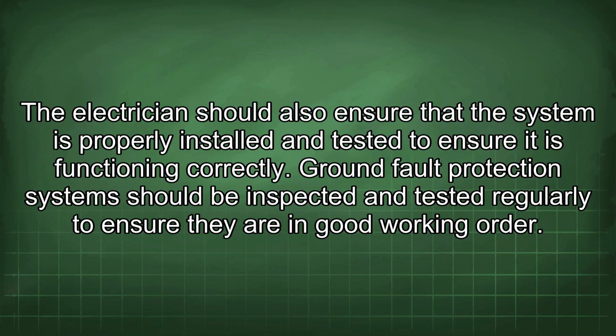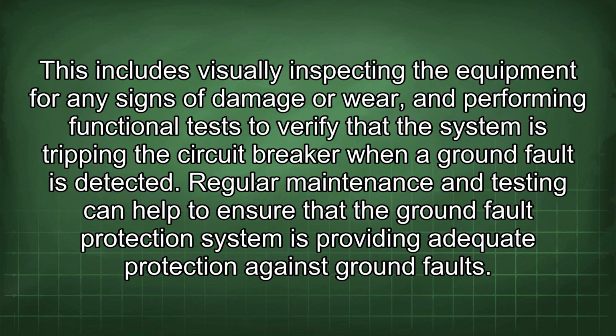Ground fault protection systems should be inspected and tested regularly to ensure they are in good working order. This includes visually inspecting the equipment for any signs of damage or wear, and performing functional tests to verify that the system is tripping the circuit breaker when a ground fault is detected. Regular maintenance and testing can help to ensure that the ground fault protection system is providing adequate protection against ground faults.